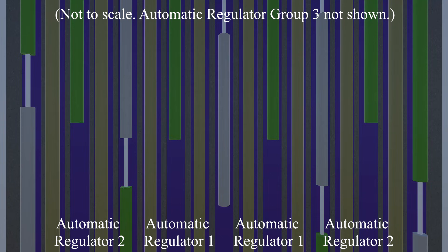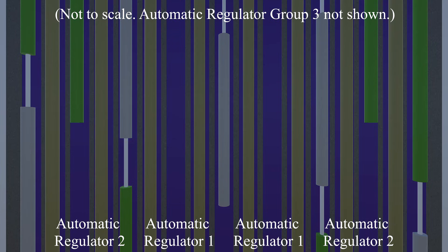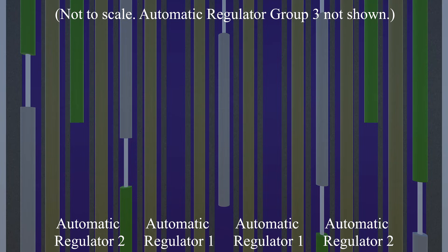The first of these comes online, and detects the reactivity in the core is lower than the power level the automatic control rod is set to. This causes all four control rods in the group to fully withdraw. Then, the second group of control rods comes online. And this time, the imbalance in the core is so extreme, they cannot move at all. And the third group, which acts as a reserve, doesn't come online either. So now, there are no automatic regulators working in the core.